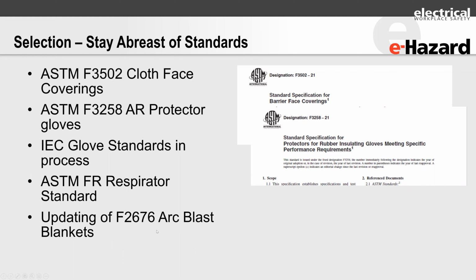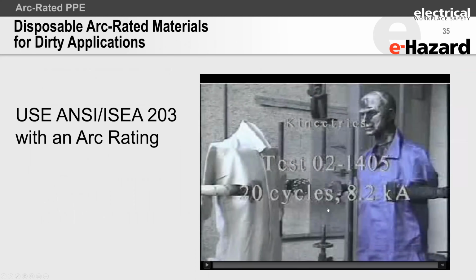And then an FR respirator standard, there's some respirator standard work happening right now in, I forget which group in ASTM, but it is for firefighters. Those should help create opportunities. There's a lot of research now being done on that because of people needing to wear respirators while also having arc flash hazards. And then we're recently working on updating the arc blast blanket standard, which is very useful if you have applications where you want to shunt arc blast away from workers who may or may not be properly protected. So it's an important standard to use.